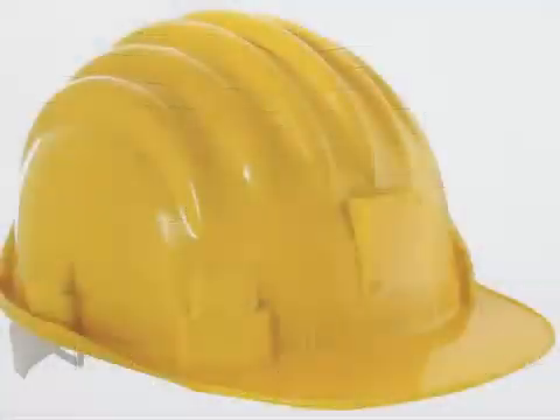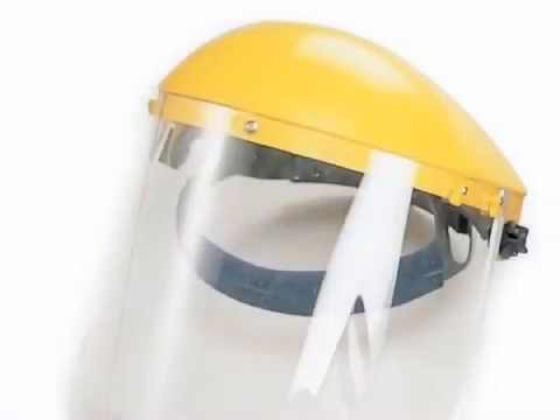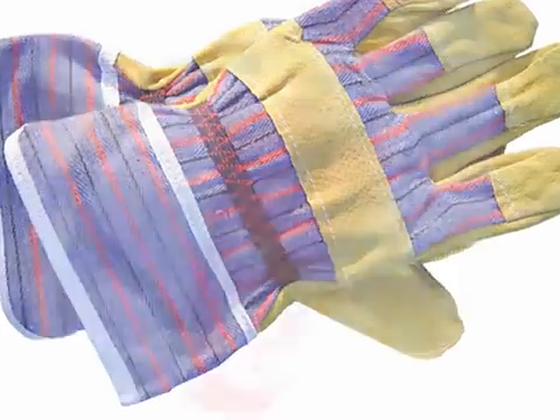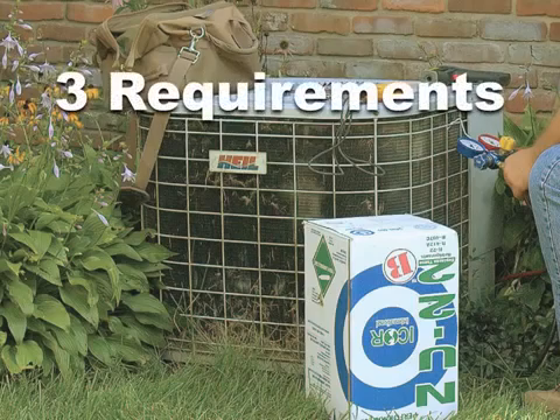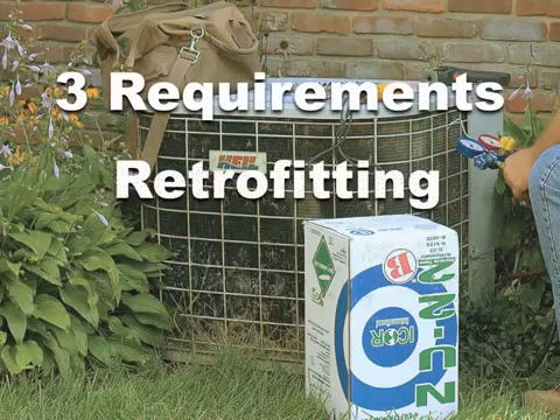It's always recommended to follow industry safety standards when servicing any air conditioning or refrigeration equipment. Failure to follow these standards could result in injury or equipment failure. Icor recommends following these three requirements when considering retrofitting to NU-22B. Requirement 1: the system must be designed for use with R22 or R407C, free of leaks and in sound operating condition.